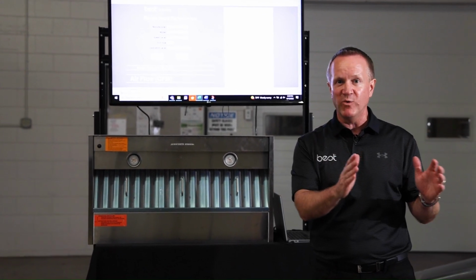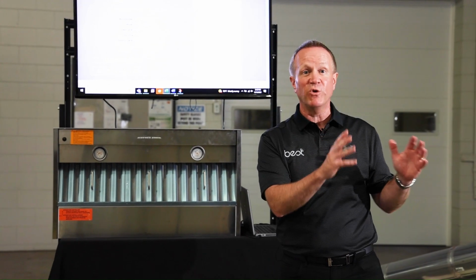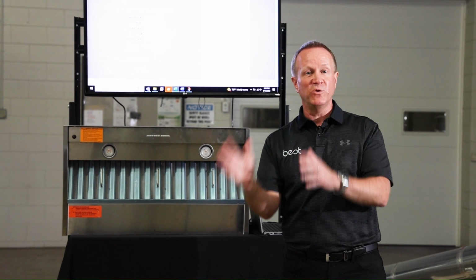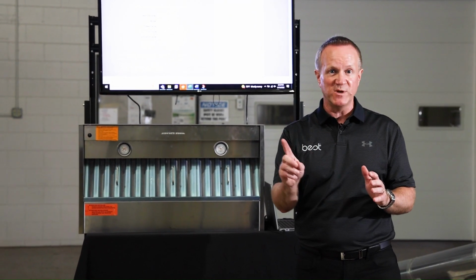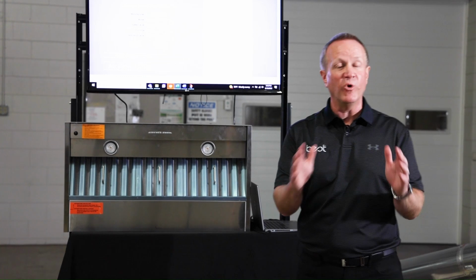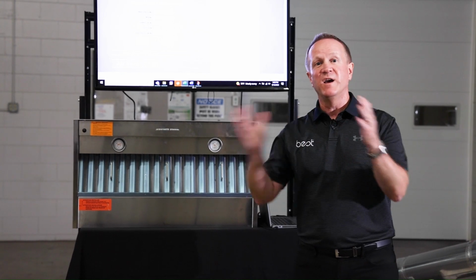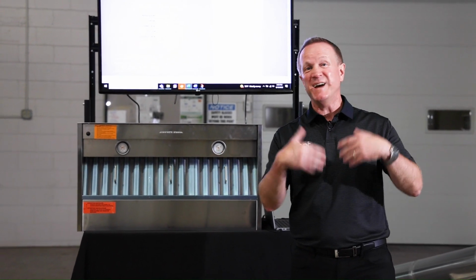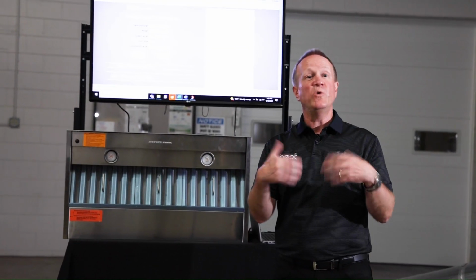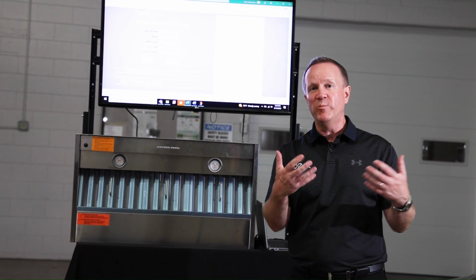The guaranteed performance system is designed so that if you buy an IQ6 blower, you're going to get 600 CFM or as close to it as possible. IQ12, you're going to get 1200 CFM or as close to it as possible. Now, why do I say as close to it as possible? Because there are scenarios where even the IQ6 is not going to be able to overcome the installation. Let's say you've got 6 90-degree elbows. Let's say you've got 140 feet of duct run. Let's say you've got 6-inch round ducting instead of 8-inch round ducting. You can stress the blower so much that it won't be able to compensate and give you that full 600 or full 1200 CFM.